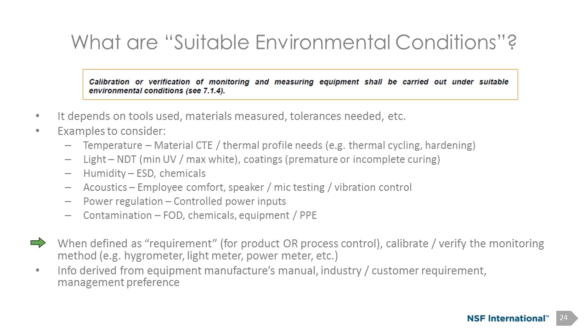When defined as a requirement for product or for process control, we need to calibrate or verify the monitoring method. Meaning if my environmental or my calibration lab is requiring 68 to 72 degrees and 30 to 60% humidity, now whatever tool I'm using to monitor that environment, so that I have confidence in the outputs of that, really needs to be calibrated. So there's a hygrometer, a temperature and humidity gauge hanging on the wall. We need to have that gauge calibrated so that it's able to demonstrate that expected requirement has been met.